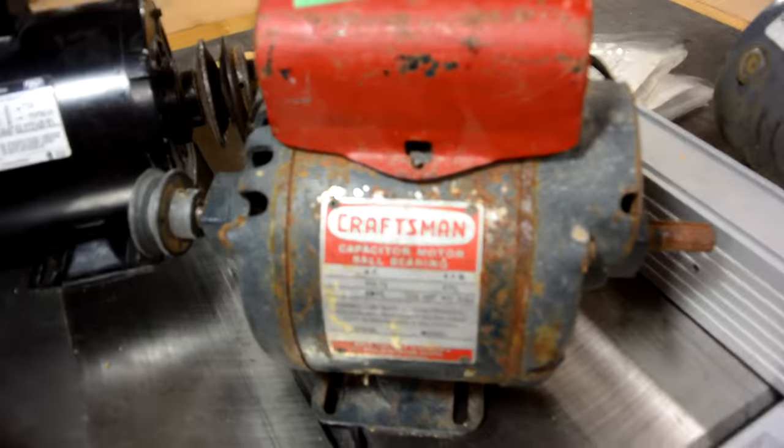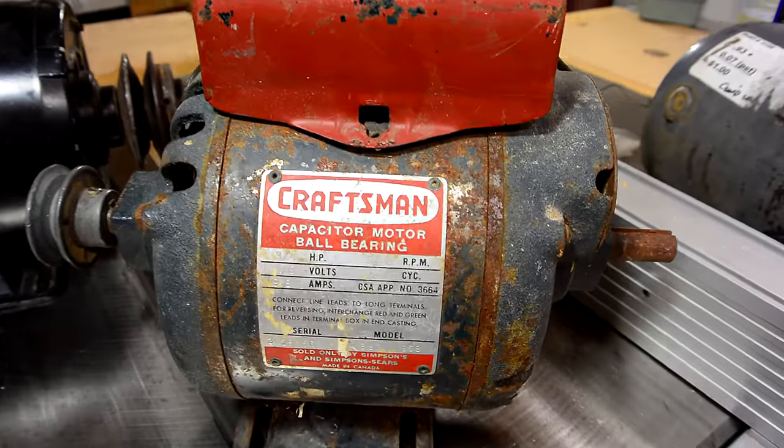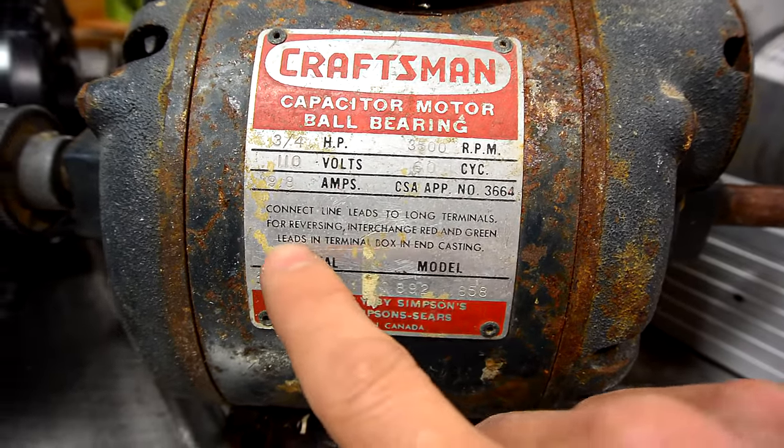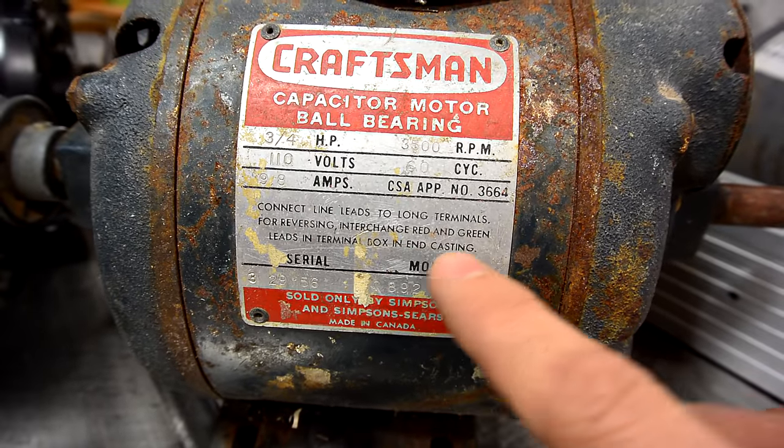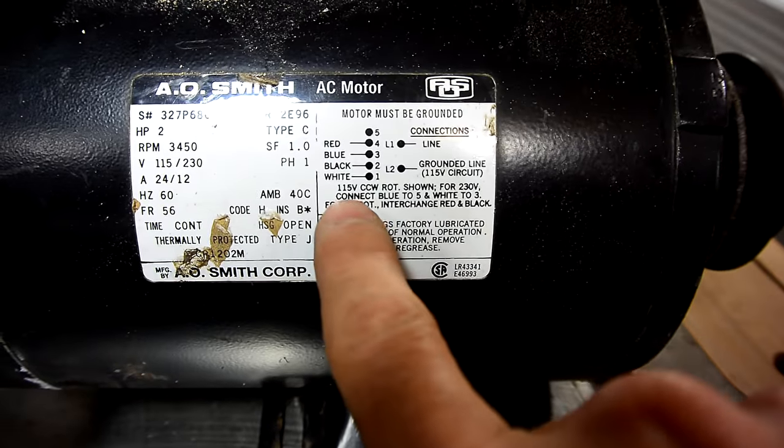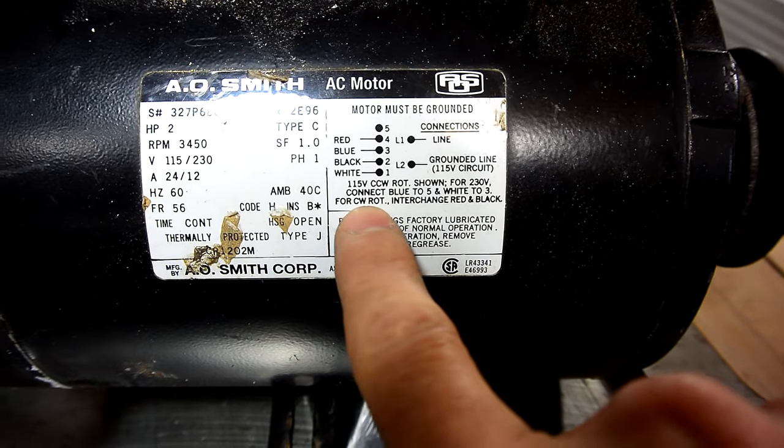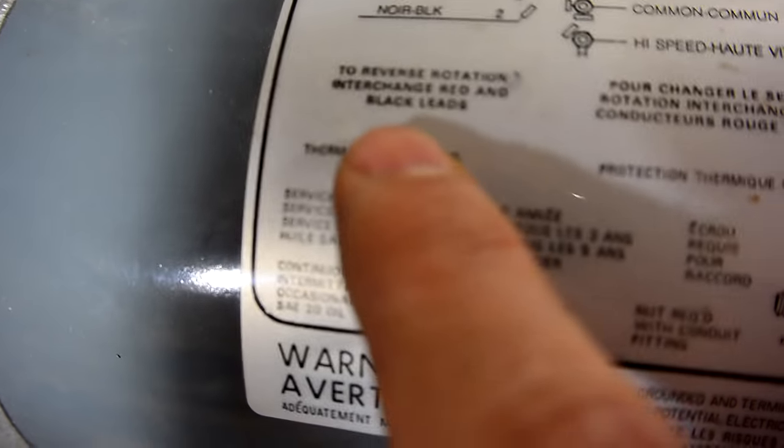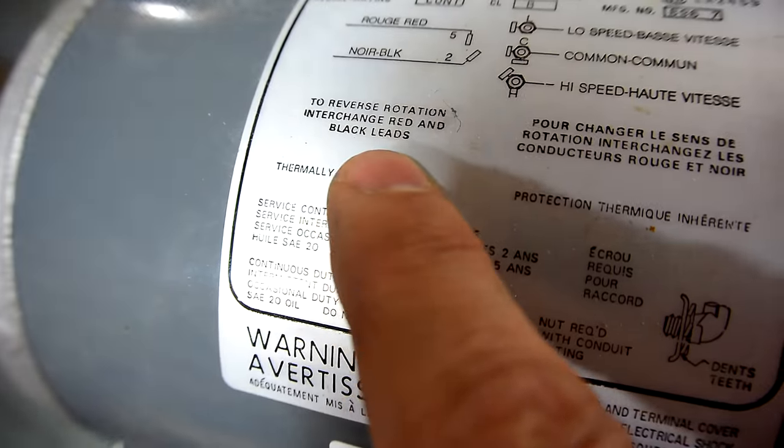But these motors here can be reversed and reversing is always reversing the starter winding. See here for reversing, interchange red and green leads in terminal box in end casing. Basically reversing the polarity to the starter winding. On this one it says for counterclockwise rotation, interchange red and black. Again reversing the starter winding. And on this one it says to reverse rotation, interchange red and black wires. So reversing a single phase induction motor is always a function of reversing the polarity to the starting winding.